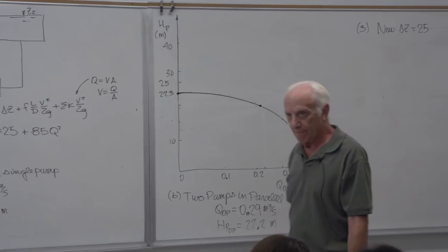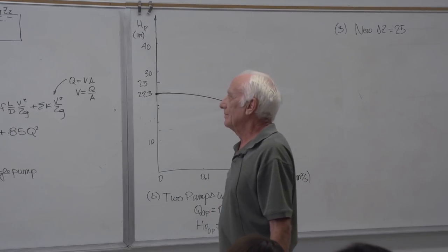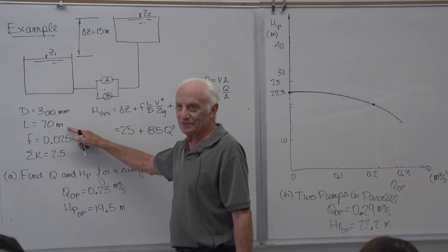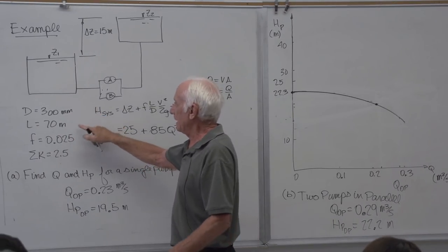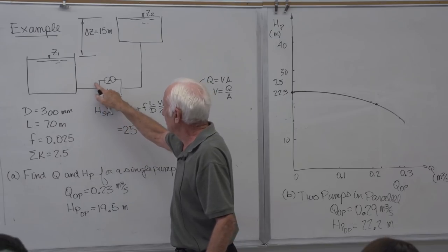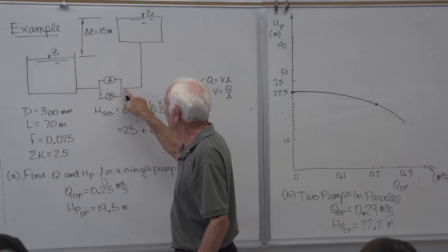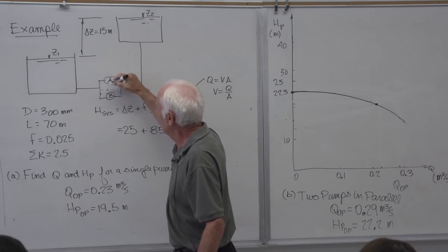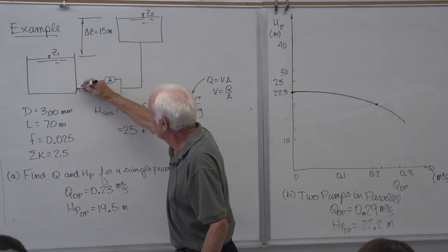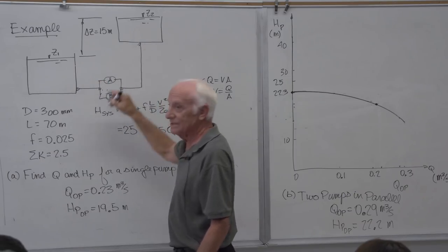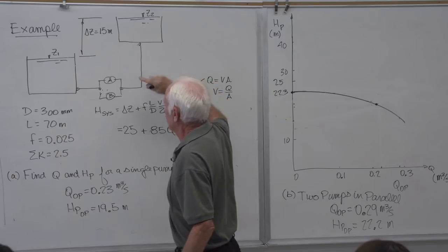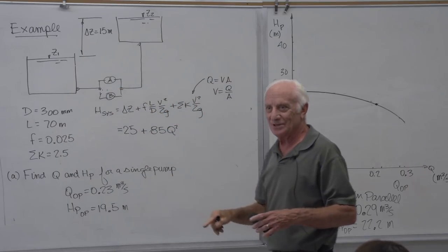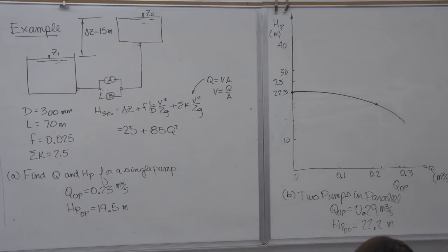Do we add any length to the pipe for the friction head? No. That pipe is so long, you might add 2 meters or something like that, but no. I mean, that length of pipe, 70, is this piece plus this piece plus this piece. You don't really include these losses in here. Really, what it is, is from here to here, and from here to here. That's the 70, this plus that. For these guys, it's assumed the pipe goes into the pump real quick, so you don't count that; it's typically minor.